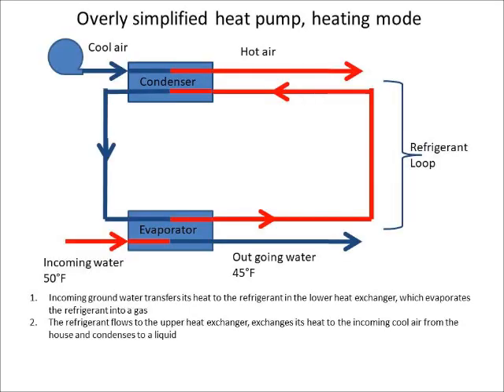This is a diagram of an overly simplified heat pump in heating mode. The incoming groundwater at 50 degrees Fahrenheit transfers its heat to the refrigerant in the lower heat exchanger, which evaporates the refrigerant into a gas. The outgoing water exits at a slightly lower temperature. The refrigerant flows to the upper heat exchanger, exchanges its heat to the incoming cool air from the house, and condenses to a liquid.